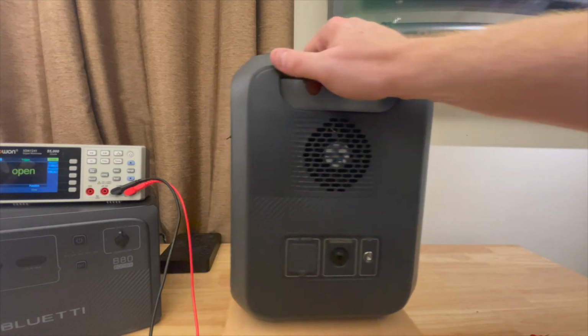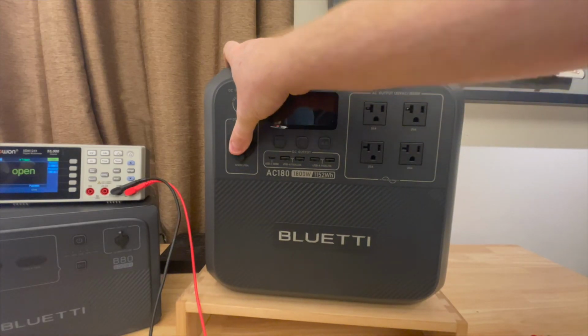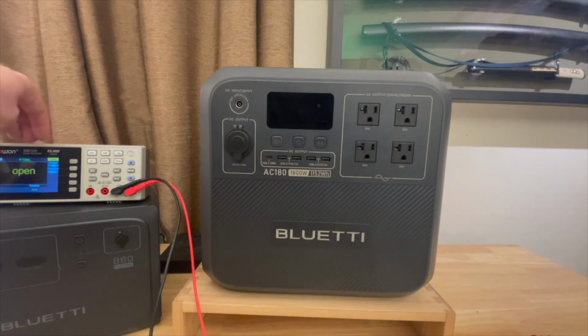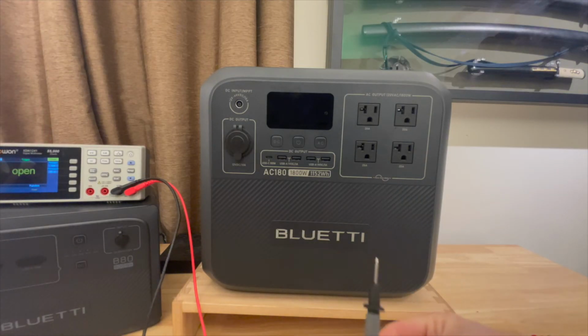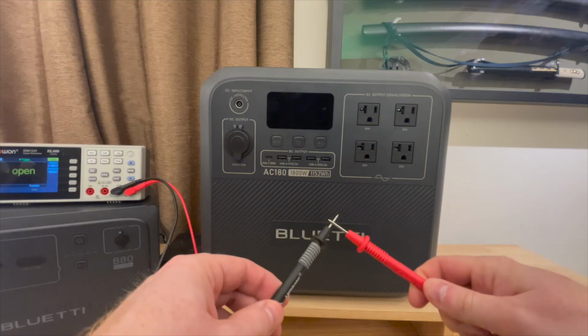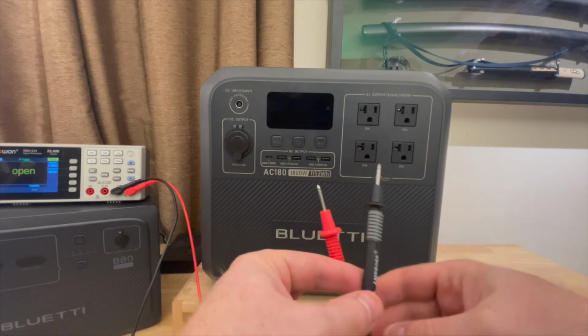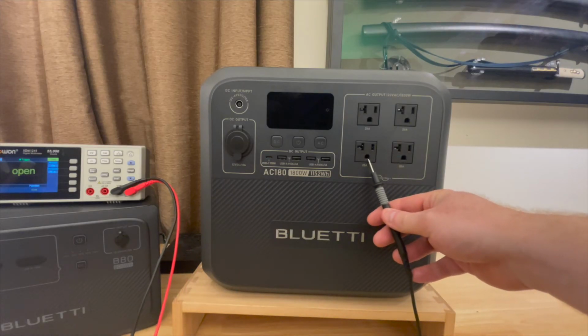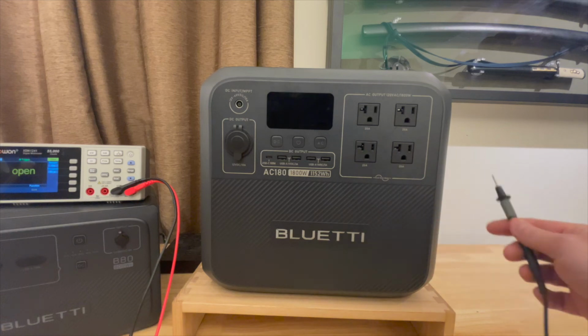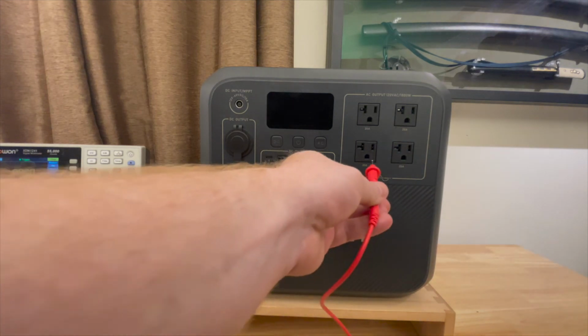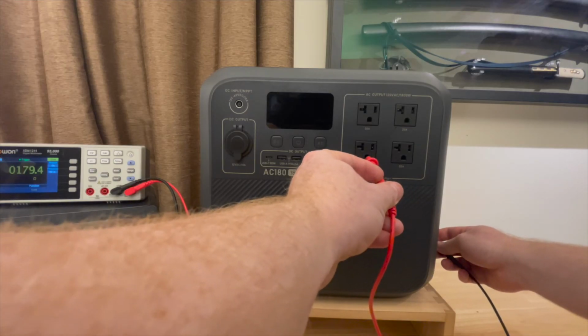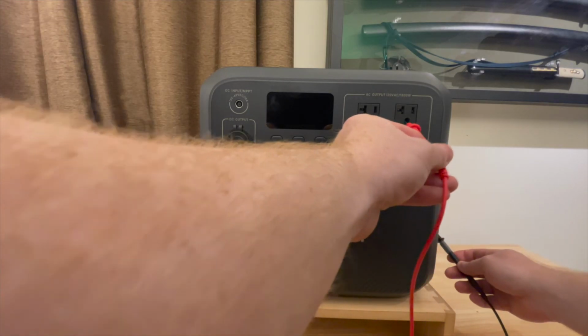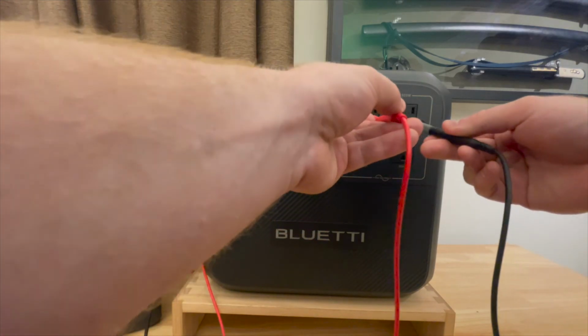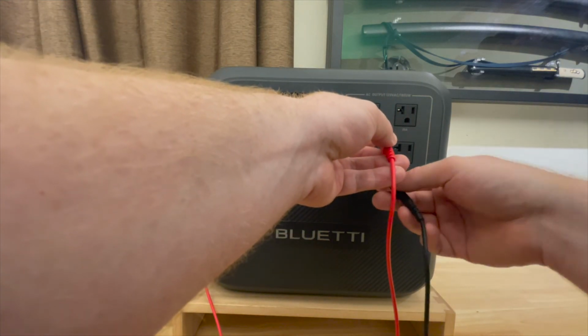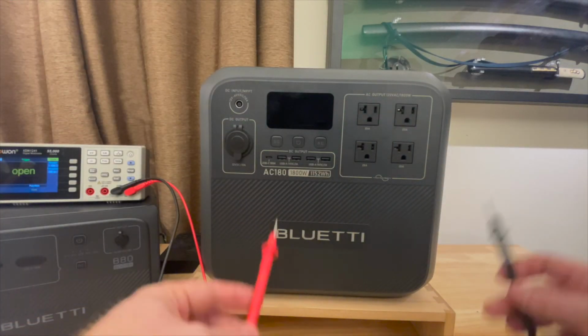Let's make sure it's actually hooked up correctly. I have this meter here that says open, which tells me if this lead is connected to this lead - when they touch, it makes a beeping noise. What should be connected is the ground lug, the bottom one on a standard US plug, to the actual metal lug on the side of the device. Let's check each one: here's one, good. Next one, good. Next one, and the fourth one - very nice. And they should be connected to each other. Yep, all four of these are connected to each other, and they're connected to the lug on the side, exactly what I'd expect.